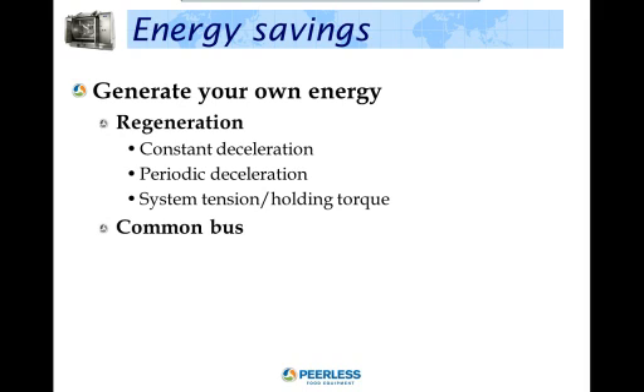In each of these examples, the motor and drive combination has the ability to recover the electrical power produced by the motor when it is acting as a generator, and send that power to the utility company. How much energy is saved is dependent on the application, but it can be significant. One such application where significant savings can be recovered is a gearbox test stand. When the gearbox is tested, one drive and a motor are used to turn the gearbox, while another drive and motor are used on the other end of the gearbox to simulate the load. Done correctly, this application will operate with a very low amount of total energy, as the amount of energy used to turn the gearbox is the same amount of energy that is recovered from the simulated load on the gearbox, less the losses in the system.